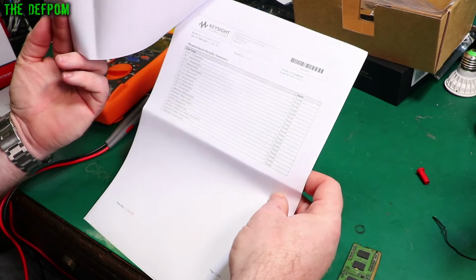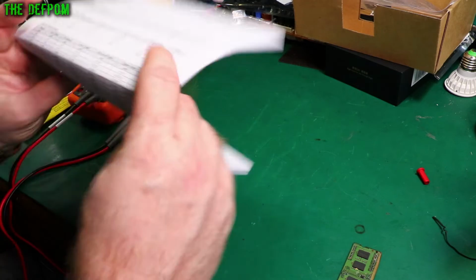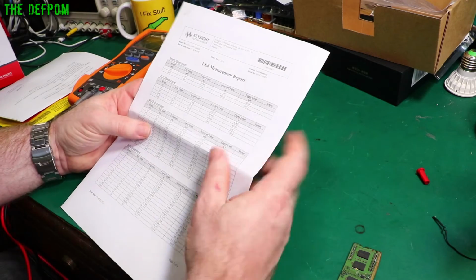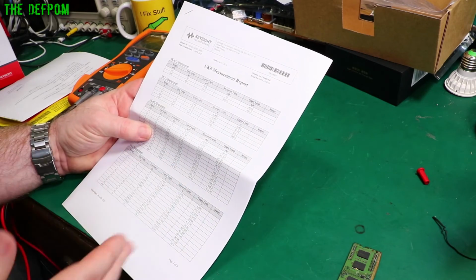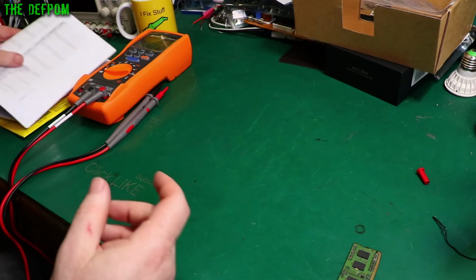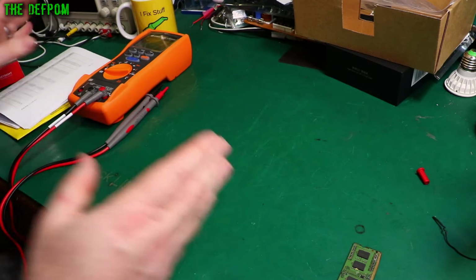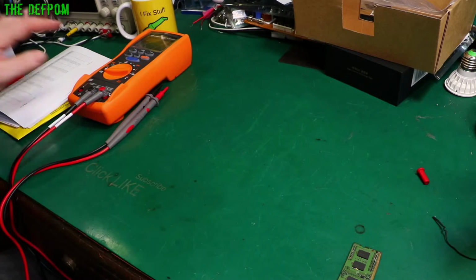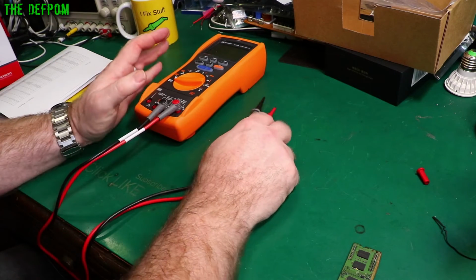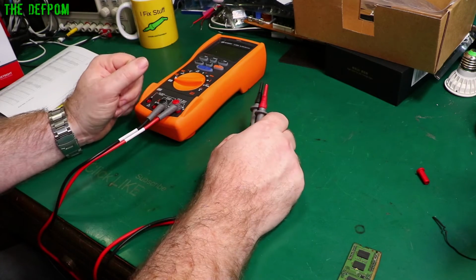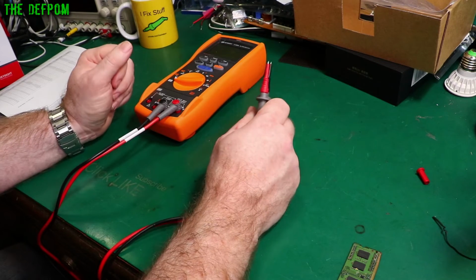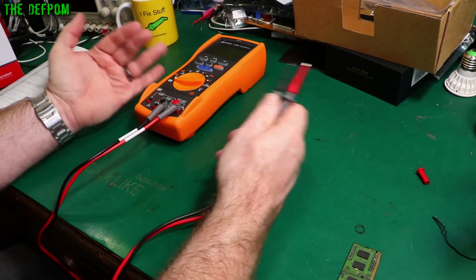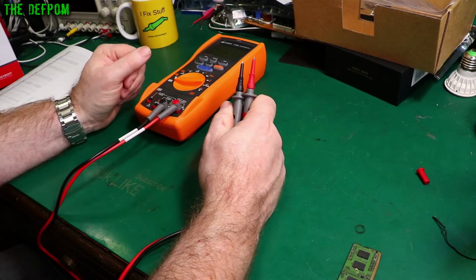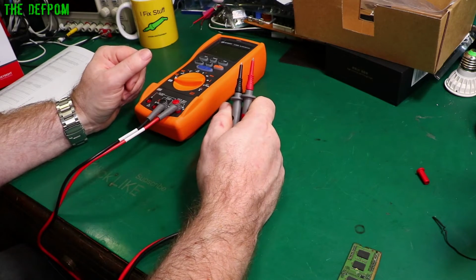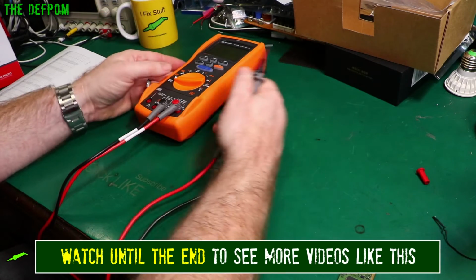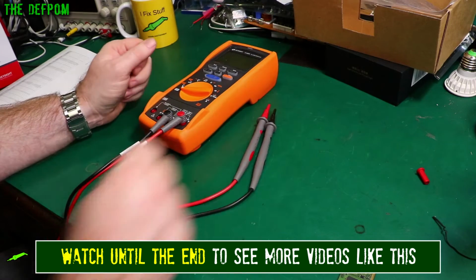It's probably going to get washed out because of the way I've got the camera set up, but yeah. So I've got all the calibrated values here, so I know exactly what it actually measured when I did the calibration, which is great. It's always nice to have a starting point so you know exactly what you've got. I've looked through most of these calibration measurements, and at least at the time of calibration, this one's very, very accurate. Obviously you do get drift over time with aging and that sort of stuff, but as it's been sitting in a box for, I don't know, 3 months, and I think it was made 3 months ago, so it's still relatively new, the calibration should still be pretty accurate, so it should be quite informative.